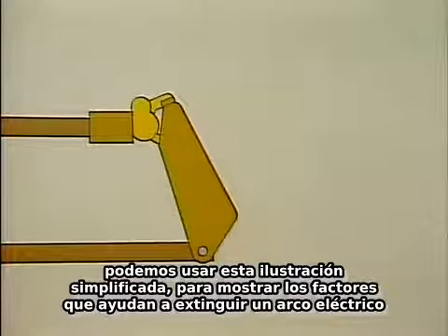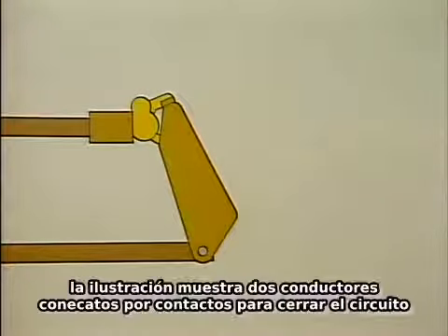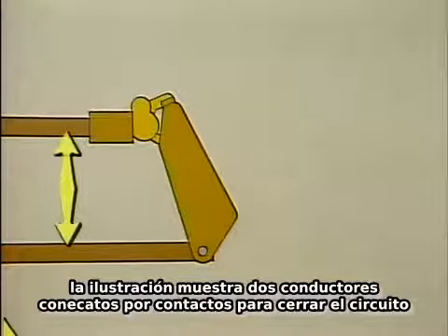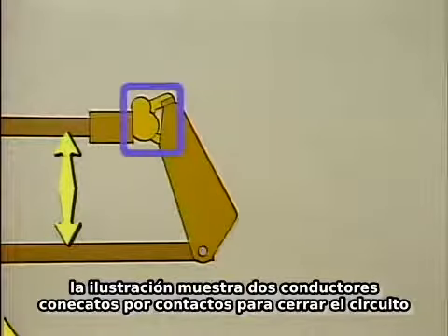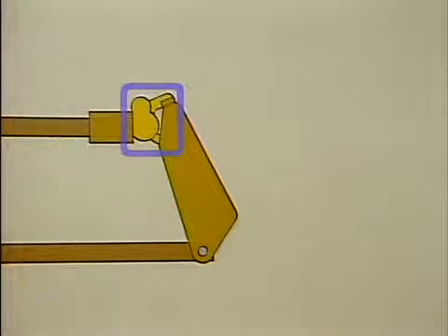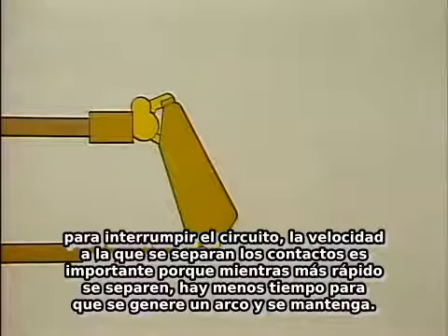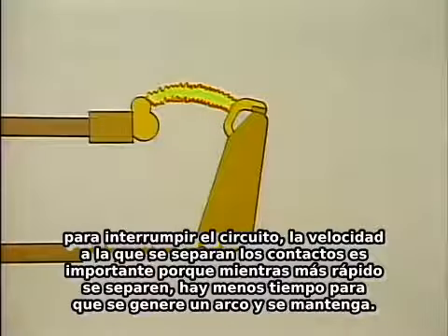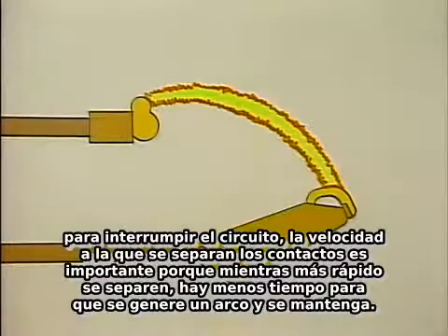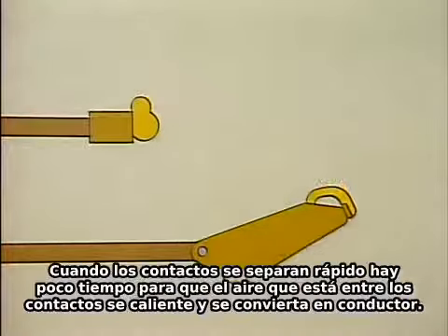We can use this simplified illustration to demonstrate the factors that help to extinguish an arc. The illustration includes two conductors connected by contacts to make a circuit. To break the circuit, the speed at which the contacts separate is important, because the faster the contacts open, the less time there is for an arc to form and maintain itself. When the contacts separate rapidly, there is little time for the space between the contacts to heat up and become a conductor.